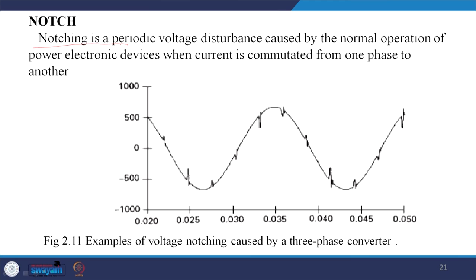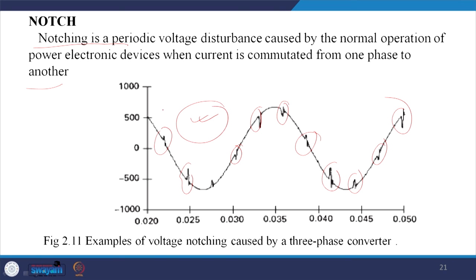Moving on to notches: notching is a periodic waveform disturbance caused by the normal operation of power electronics devices when current is commutated from one phase to another. This can be seen clearly in most converters. After every 60 degrees, one pair of thyristors is conducting and then it switches to another pair — each such commutation event produces a notch. This waveform distortion requires elimination from both a power electronics and a power quality perspective.